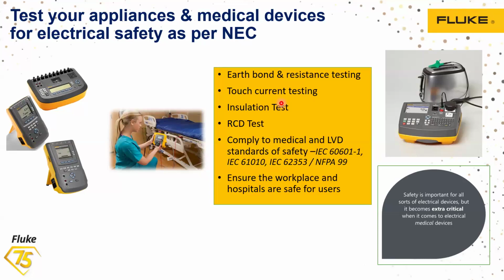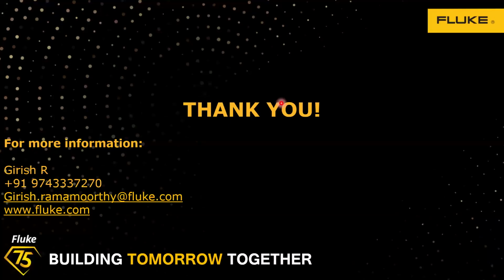So here, checking all the electrical installations, MCBs, their loop impedance, RCDs, and the earth looping, all these points need to be tested on a regular interval basis. Ultimately, this is for the safety of everyone, right? These tests need to be carried out regularly to avoid unwanted electrical shocks, or to protect your assets from being damaged because of the high fault current flowing through. With that, I've come to the end of the short presentation. If you have any queries about this, we are free to answer.